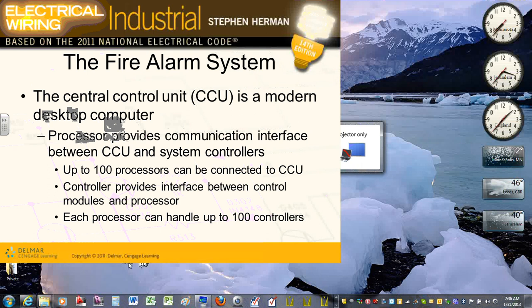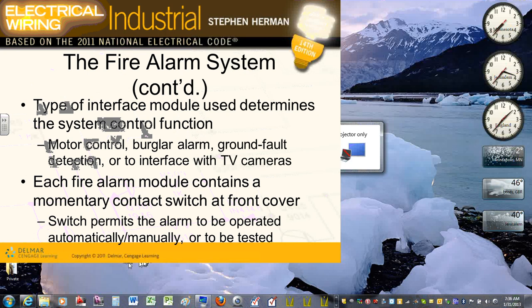So when you design a system, guys, a fire alarm system, the most important thing for a fire alarm system is to indicate how many input devices you need and how many output devices you need. And my understanding right now, and Darren, I'm not an expert in the fire alarm system, my understanding is you can put hundreds and hundreds of devices on one signaling line circuit, because they're all digital. You send a signal to them, and they're monitored digital devices.